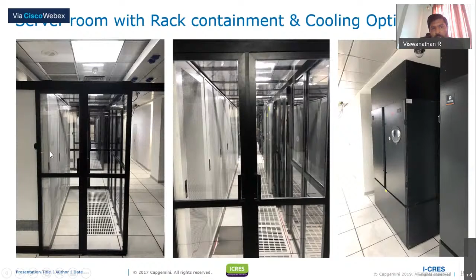which is being spent otherwise on a PAC. If you can see this area, these are void space areas where you cannot see any grills. The grill area in front of the rack is closed through a containment, so this void area is free and no cooling takes place here, only the rack is cooled. So the rack gets better cooling as well as our energy is reduced.